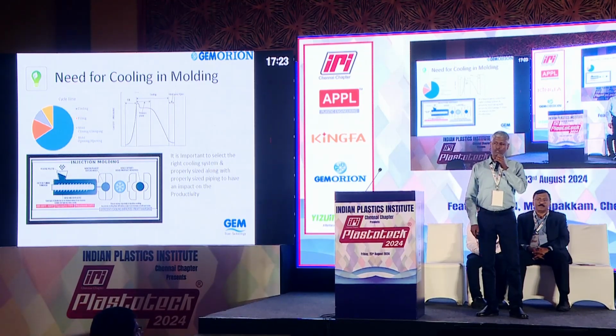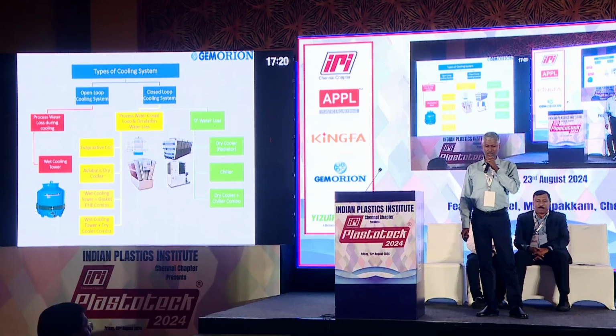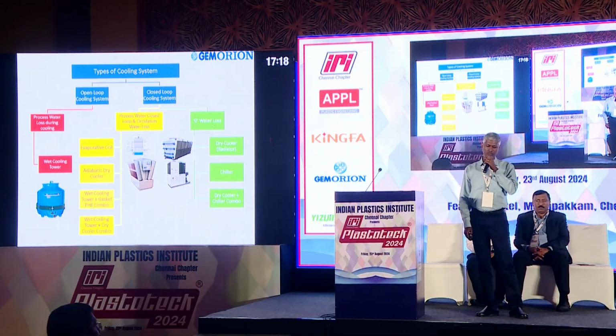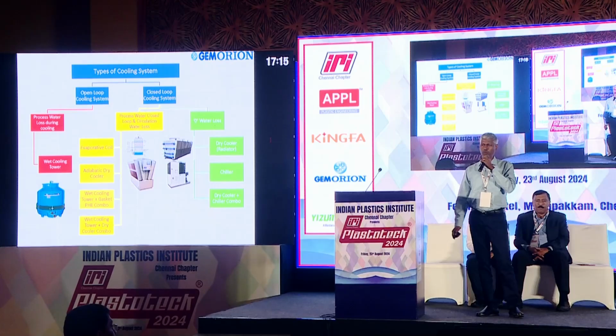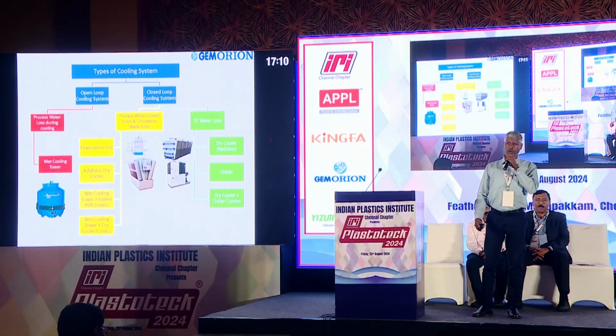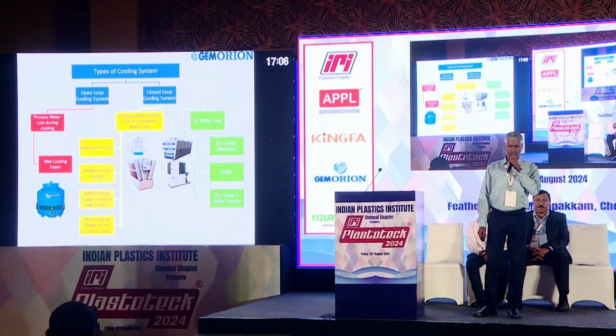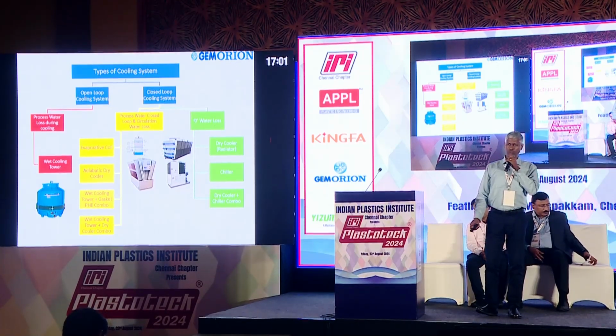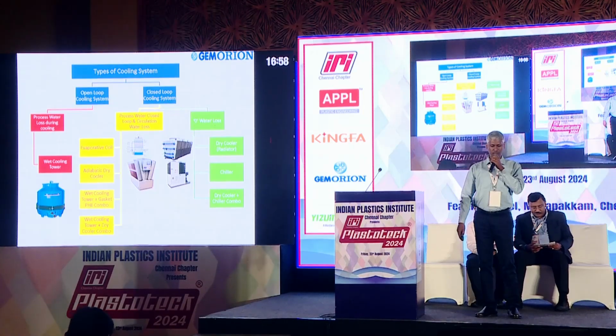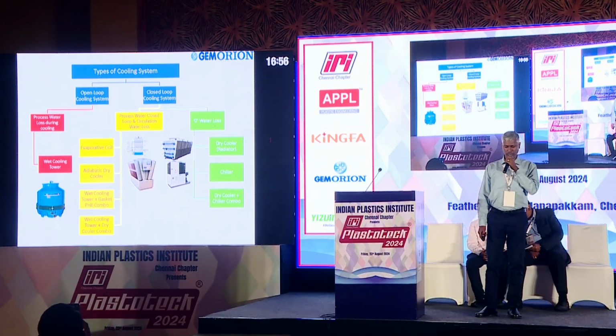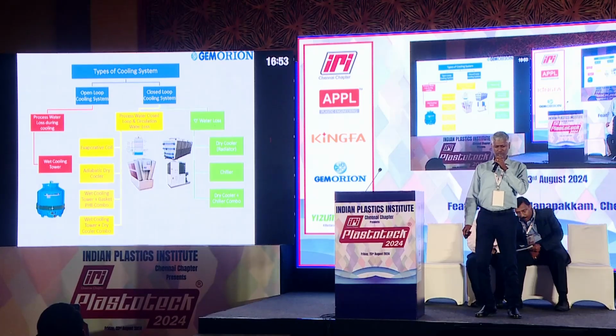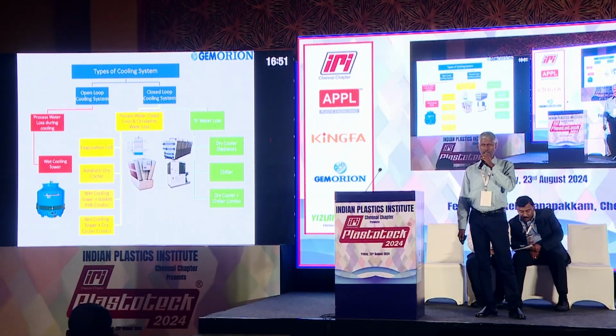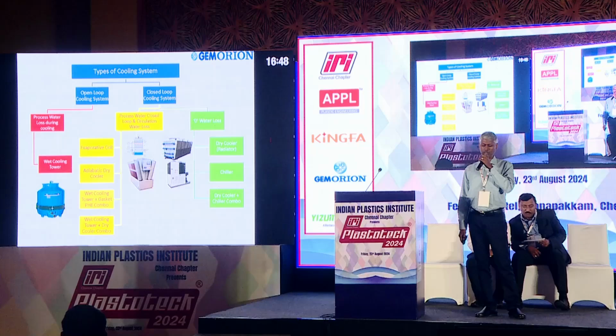Before going into how to select, let's see what types are available. We have open loop cooling and closed loop cooling. Open loop cooling is a conventional cooling tower where water evaporates and the heat is removed in the form of latent heat. In closed loop cooling, we have an evaporative coil cooling tower where the process water stays in a closed loop and is cooled by some local circulation water, then adiabatic dry coolers, and combinations of coolers. When you go to the zero loss category, we have dry coolers, a simple radiator, a chiller, and combinations.